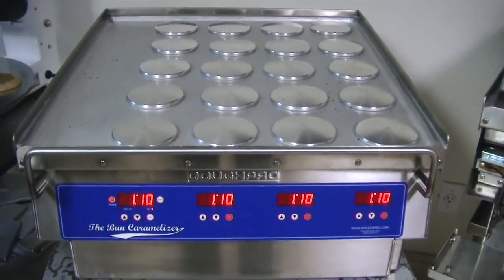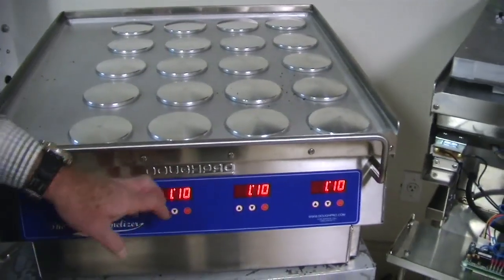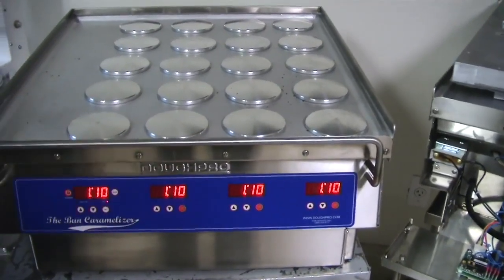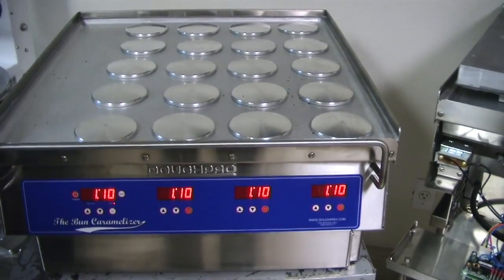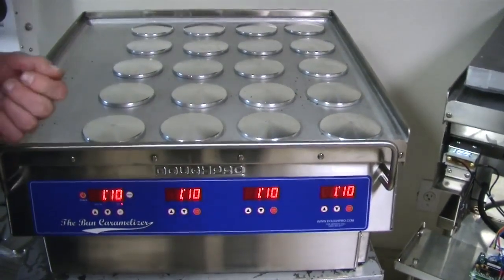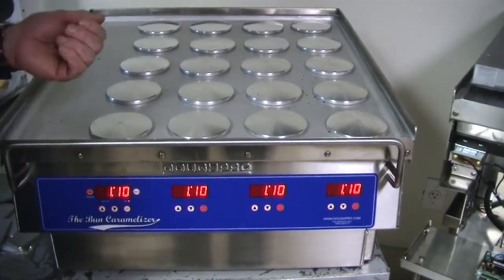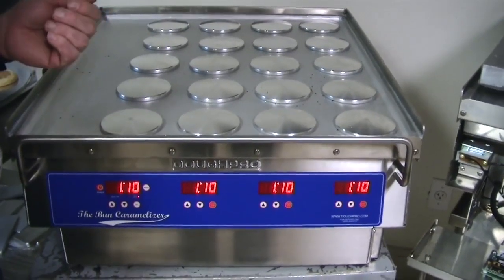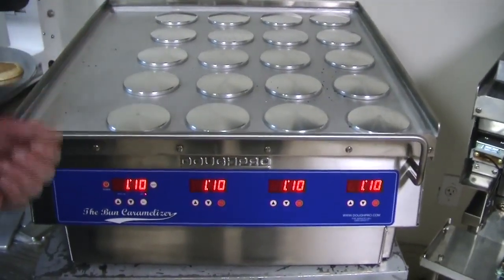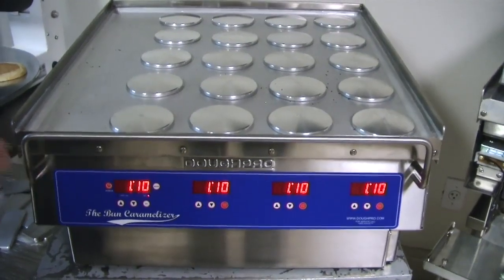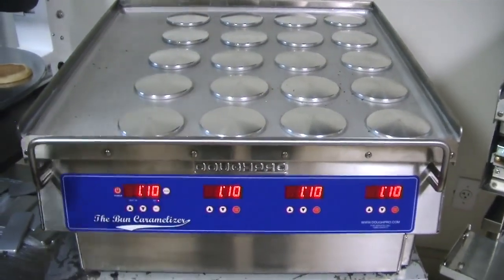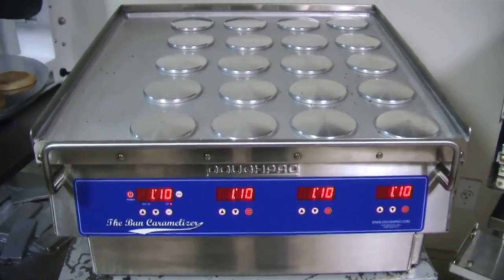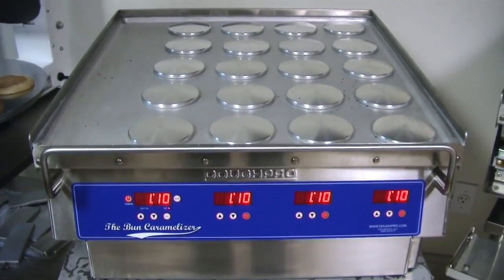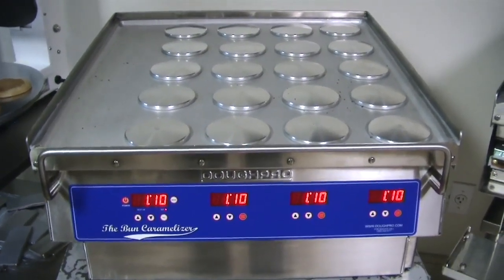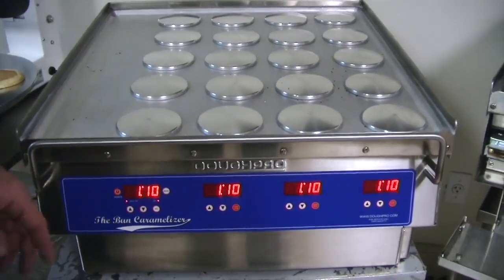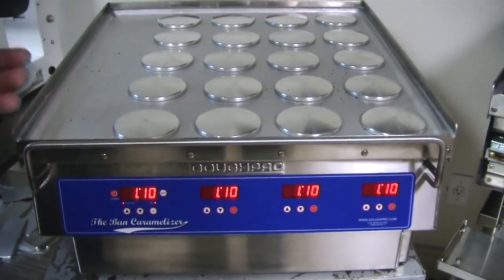Another thing that occurs is maybe there's a digital control flashing and doing all kinds of weird numbering. One way I would do it, first of all, is to unplug the machine, wait for about a minute, plug it in, and see if something got in the electrical there that caused this. Nine out of 10 times, that'll fix the problem. But if that does not fix the problem, the controller might have taken a hit. One of the components of the controller, the display chip, may be damaged, and you need to replace the controller by itself.